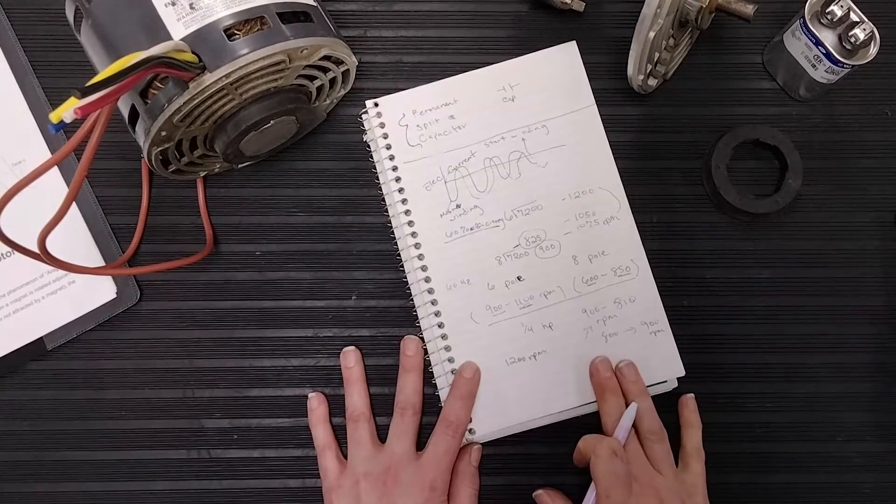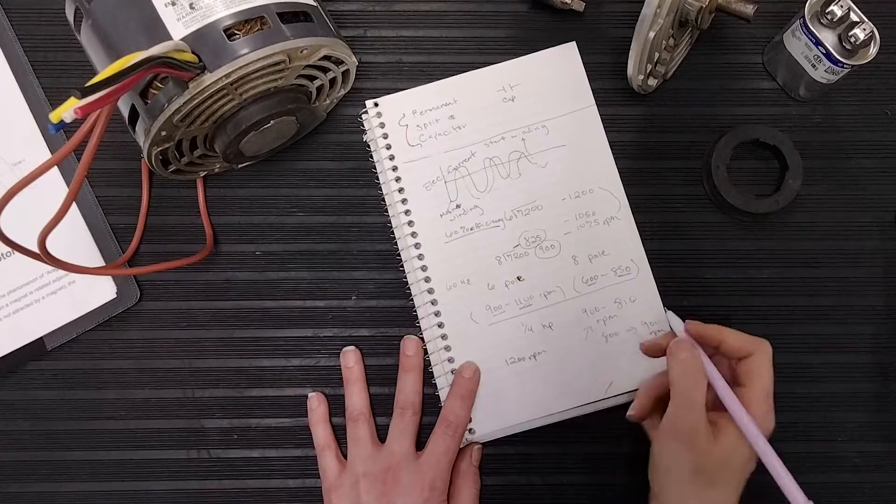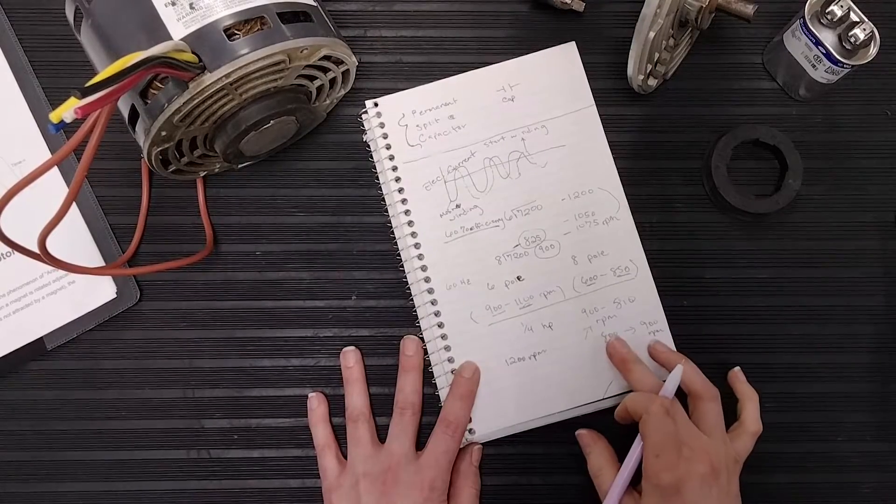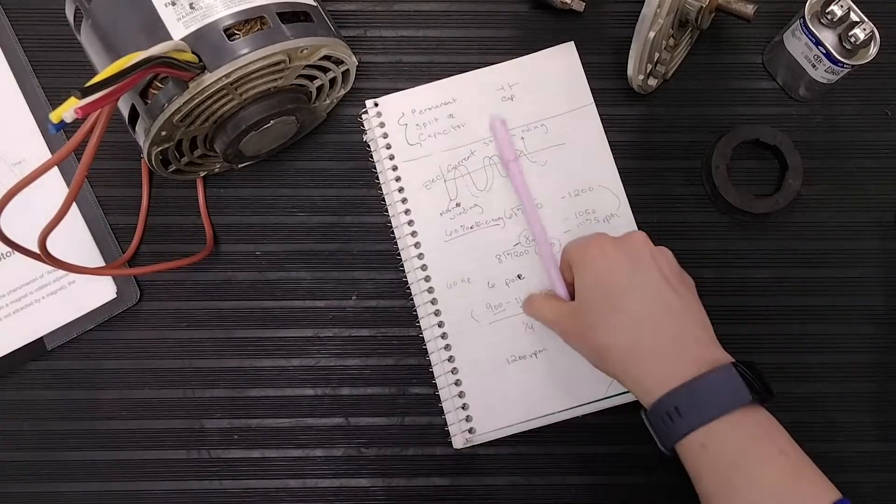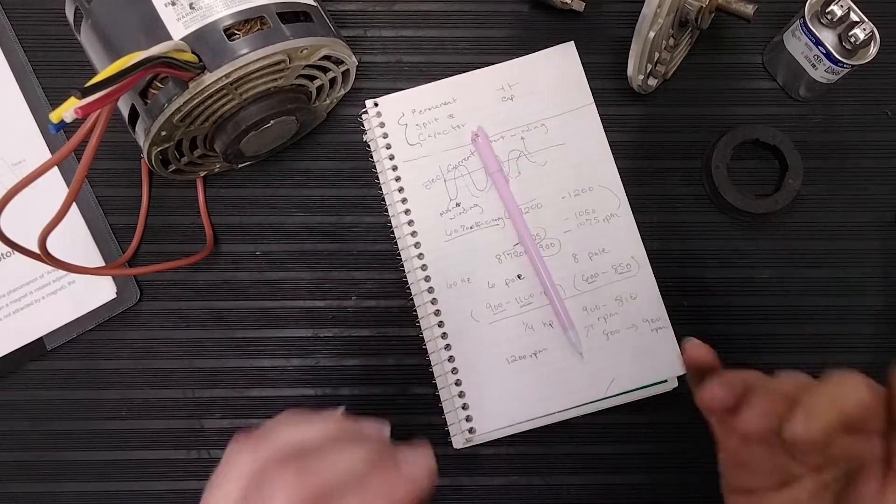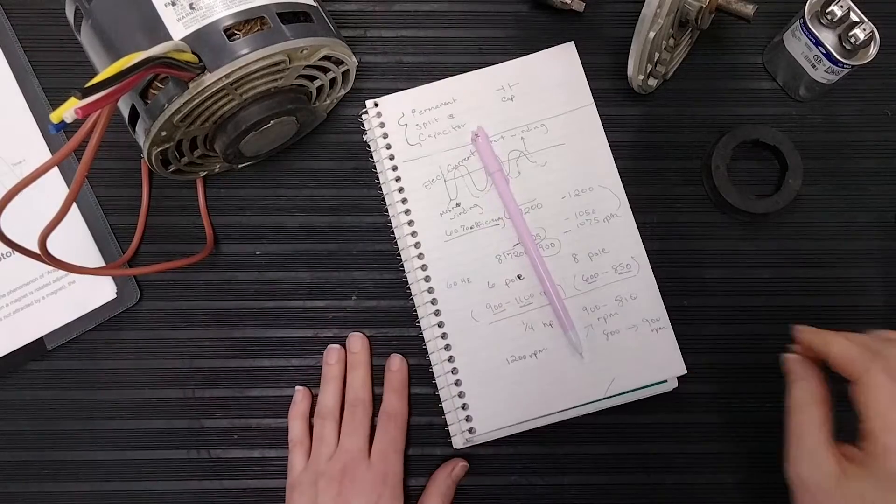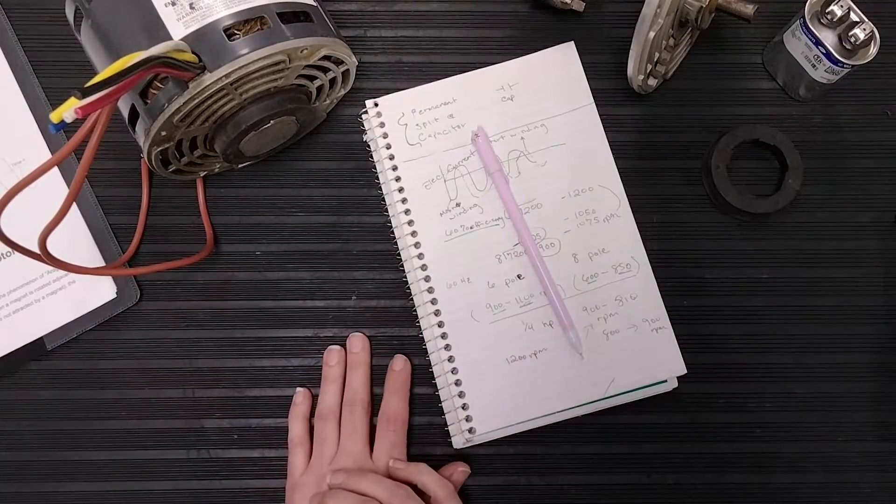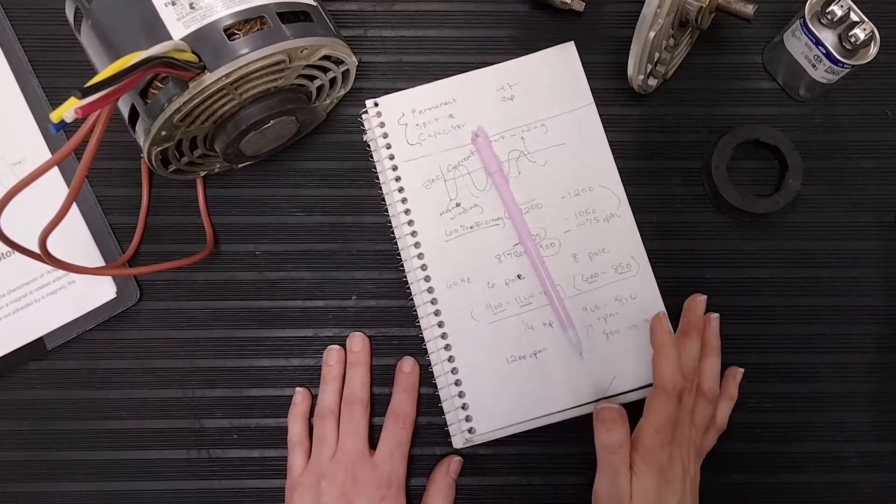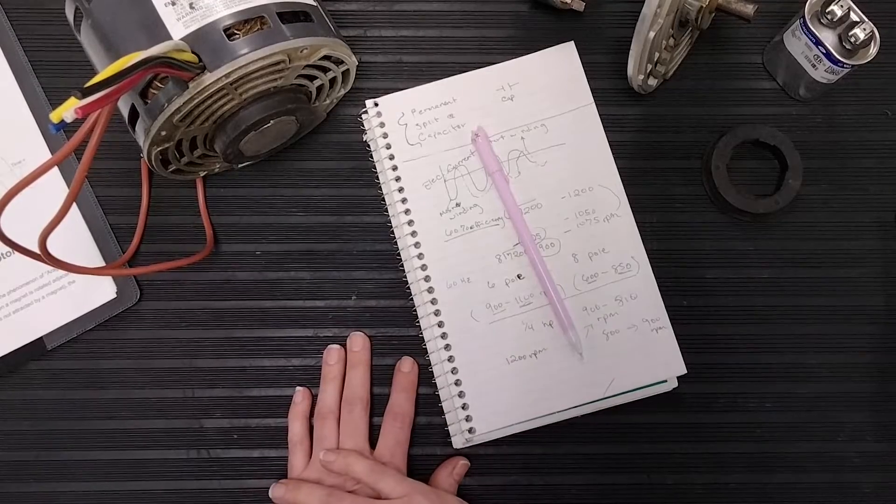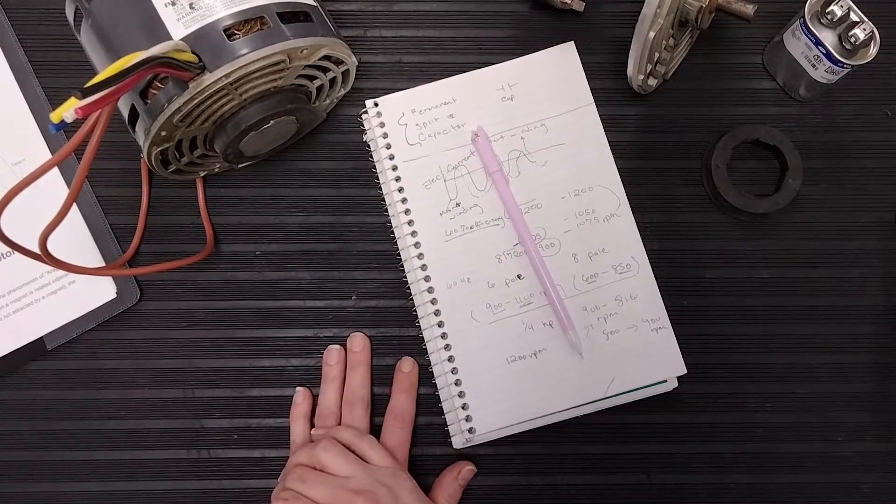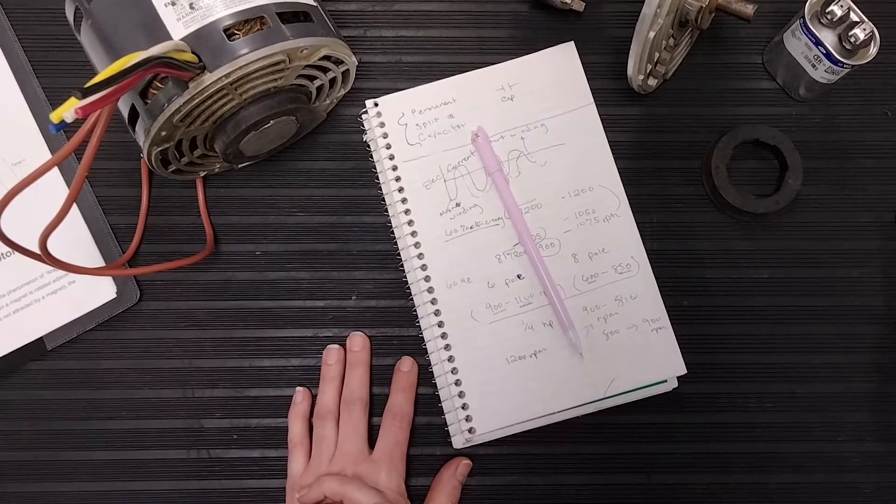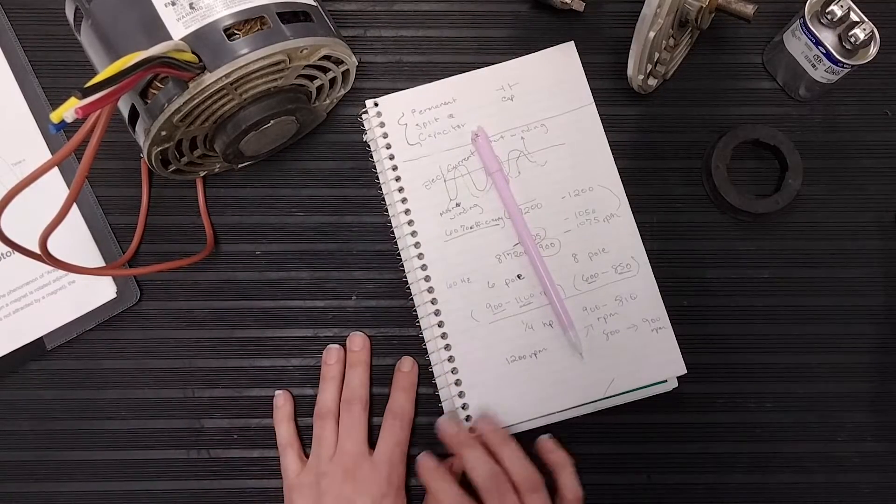Now, I've seen quite a few of the newer motors switching over to this 825 or 800 RPM. And that's because an 825 RPM motor runs a lot quieter than a 1075 RPM motor. Now, hypothetically, you could replace it that way, but then you're going to have to account for that with your fan blades.